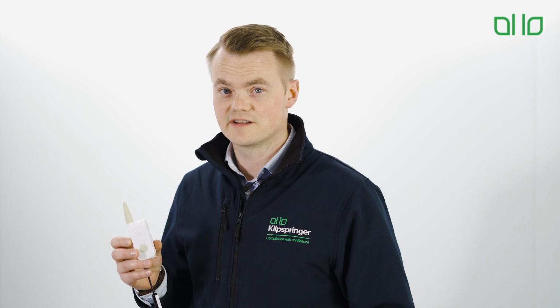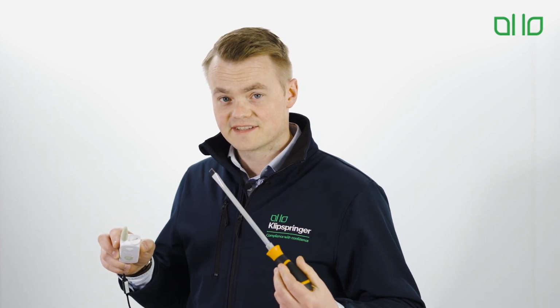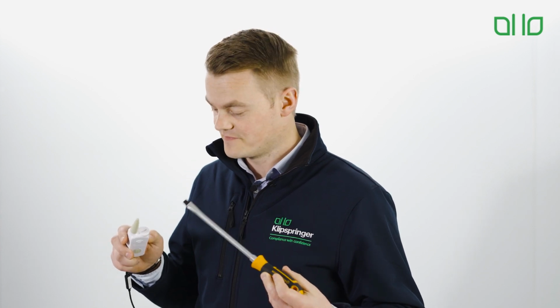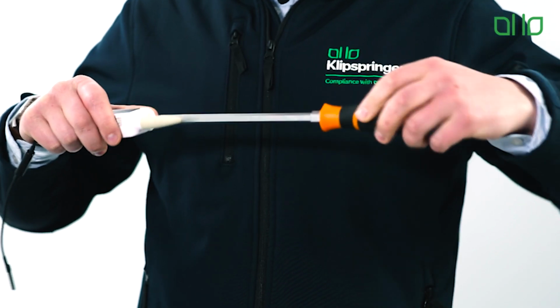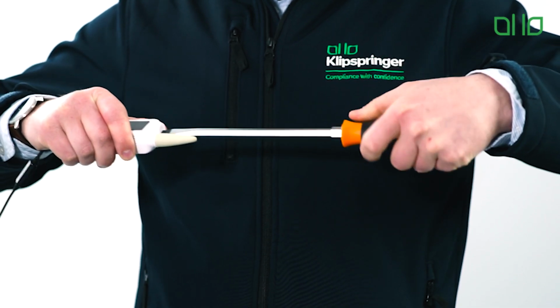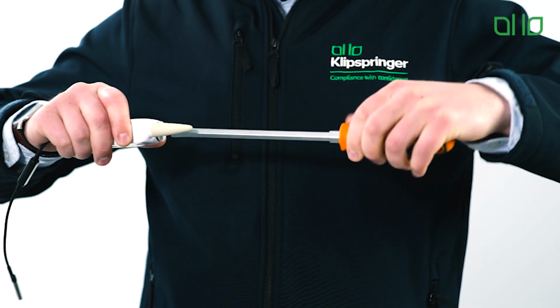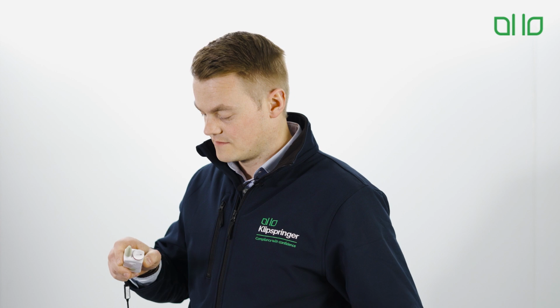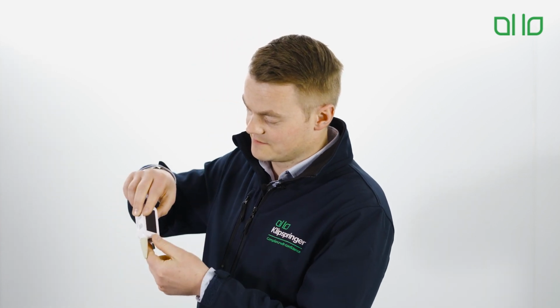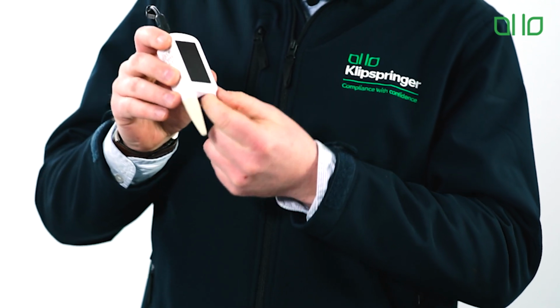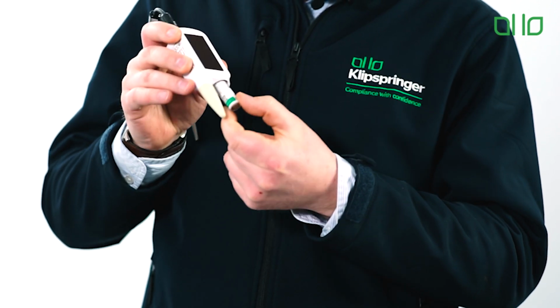On the previous version of the transmitter, to change the battery, the cap is located on the top of the transmitter housing. You can see this here. You will need a large flathead screwdriver, preferably 10mm size. Simply unscrew the sealing cap anti-clockwise. Then remove the sealing cap. The battery is located inside. Simply turn the transmitter upside down to remove the battery.